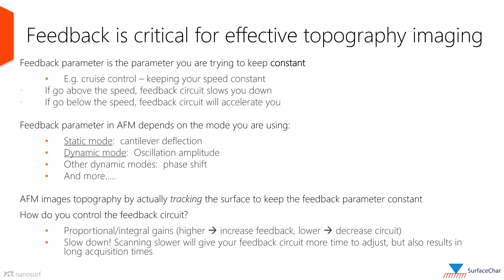AFM images topography by tracking the surface to keep the feedback parameter constant. The feedback loop operation is controlled by gain settings. The higher the gains, the more feedback. In case the feedback is insufficient, slower scans may solve the issue at the expense of taking more time.